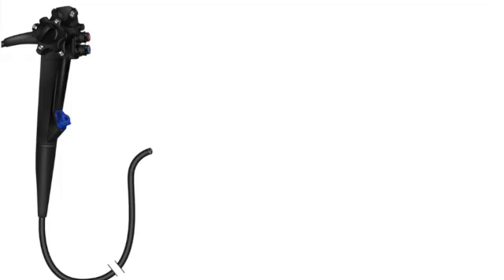Next up, insertion tube diameter. This is the actual width of the scope, usually in millimeters. For the tech prepping the instruments, this feels like the most critical safety spec. The variation can be pretty significant. Gastroscopes, you can find super slim ones, like 4.9 millimeters, all the way up to your standard 10.9 millimeters.